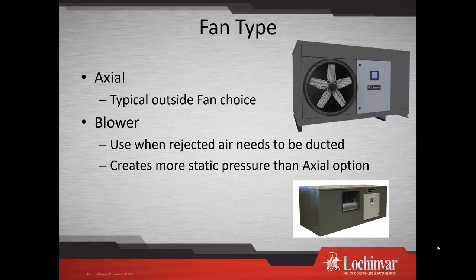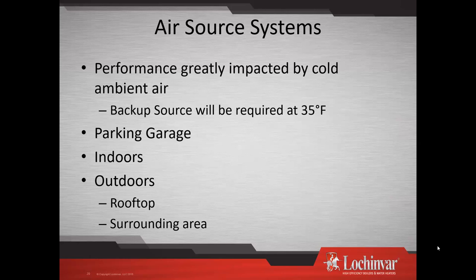And the problem that we've seen a lot, and I wish it was just residential, but also commercially, is that we have some places where we don't have waste heat. So they have a room where you're looking to put a heat pump water heater, and there isn't any waste heat. A heat pump water heater extracts energy out of that air. Well, if we don't have waste energy in that air, we're going to kick on a baseboard or an electric fan coil unit to support this. We're switching pockets, we're not getting the efficiency. So one of the most important things when making selections on a lot of these types of units is thinking, where is its true efficiency coming from, and how do I make it work for my conditions? Because it's not just this, there are other products that are being misapplied. If somebody says, okay, it has to be inside, in that case you get a blower model and you duct it to the outdoors. But then you look at the details, and let's say my power consumption's through the roof, and maybe that efficiency I was anticipating for a payoff, you're not going to get. So you've got to look at the big picture.